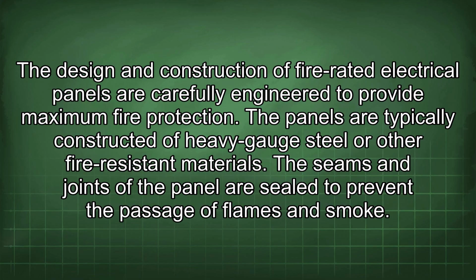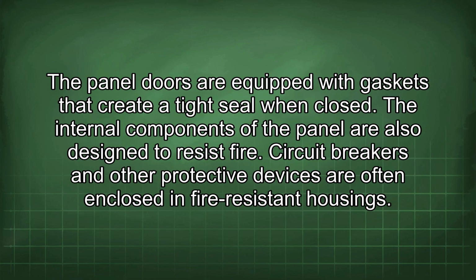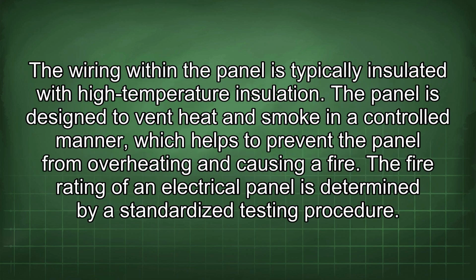The panels are typically constructed of heavy-gauge steel or other fire-resistant materials. The seams and joints of the panel are sealed to prevent the passage of flames and smoke. The panel doors are equipped with gaskets that create a tight seal when closed. The internal components of the panel are also designed to resist fire. Circuit breakers and other protective devices are often enclosed in fire-resistant housings. The wiring within a panel is typically insulated with high-temperature insulation. The panel is designed to vent heat and smoke in a controlled manner, which helps to prevent the panel from overheating and causing a fire.